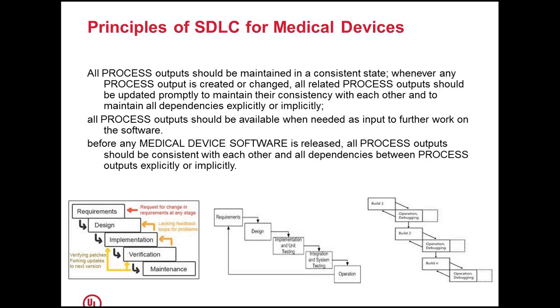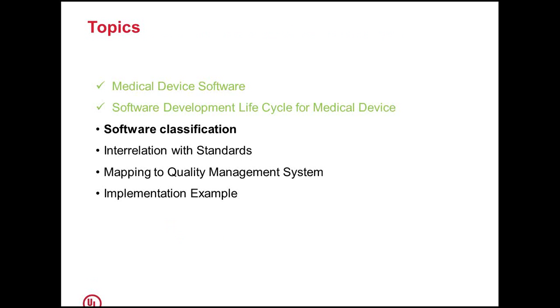Regarding medical device software release, before the software is put in use, all outputs should be consistent with each other and all dependencies between process outputs — explicitly or implicitly — must be verified and confirmed to meet requirements before release. So we discussed why a software development lifecycle model is required for a medical device, the various practices in the industry, and why it is critical for medical devices.